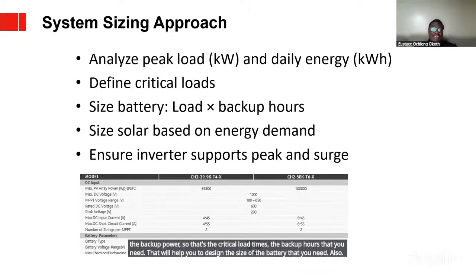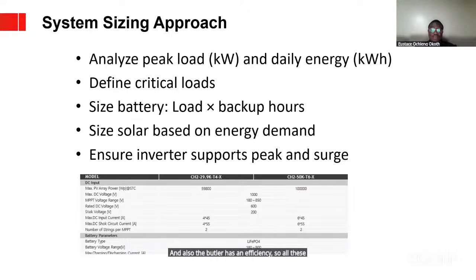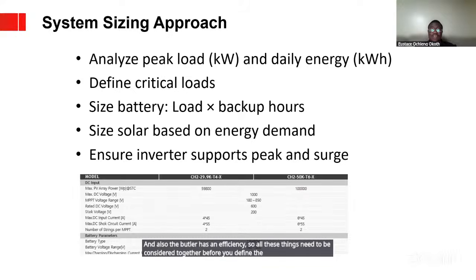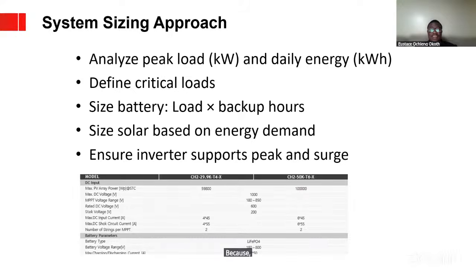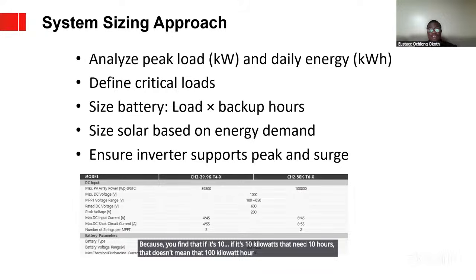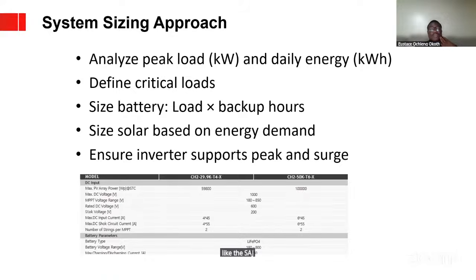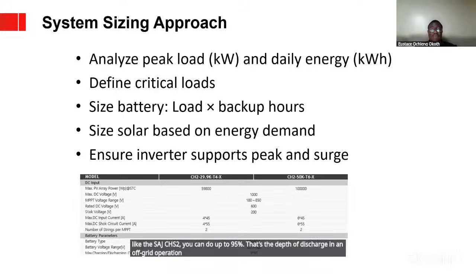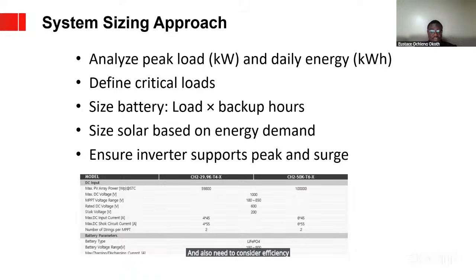Also consider that the battery has a depth of discharge. And also the battery has an efficiency. So all these things need to be considered together before you define the size of the battery capacity that you need. Because you find that if it's 10 kilowatts that you need for 10 hours, that doesn't mean that 100 kilowatt hour is enough to provide backup for this 10 kilowatt. You need to consider the depth of discharge which you're going to use. For the solution that you have, like the SAJ CHS2, you can do up to 95%. That's the depth of discharge in an off-grid operation. So that means that you need to consider that 5%, the DOD, that's the end of discharge, and also need to consider the efficiency of the system generally.